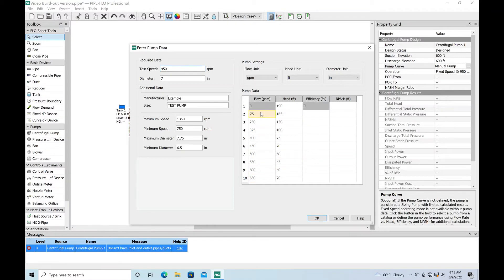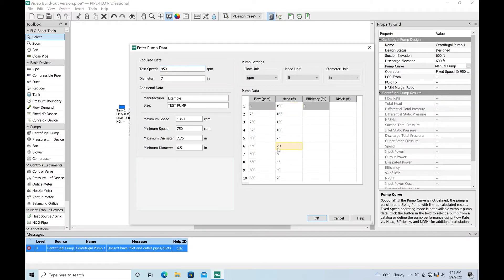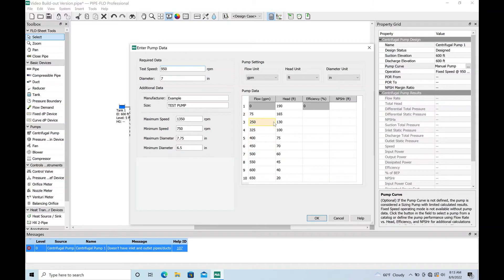A lot of times I'll build this out first just to get an idea like I've done here, sort of a test case. I know what flow I want and kind of play around a little bit. I've pre-entered flow and a flow and head curve. You can get this from your pump supplier or like I said here you can build something sort of generic just to get an idea.